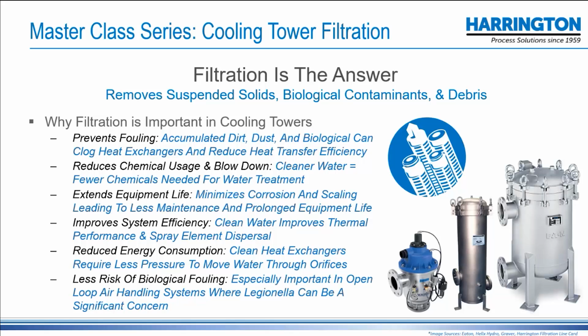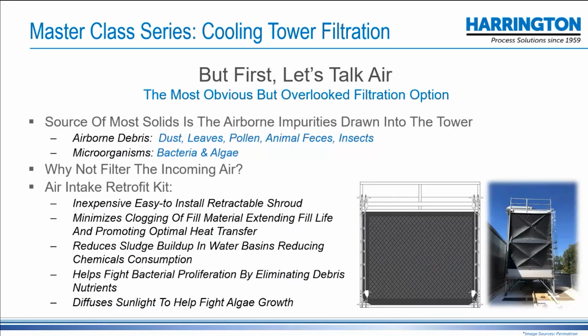Very much reduced energy consumption. You're not pumping against scale, so you're going to save on power where pumping is concerned. And you have less risk of biological fouling, which would be very important where Legionella could be a concern. So we're going to talk about water filtration. But before we do that, let's talk about air.